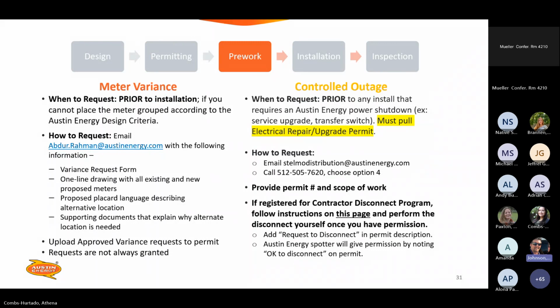A controlled outage, when to request. Prior to any installation, don't build it and try to get a controlled outage as an emergency or anything like that. You must also pull a separate electrical repair or upgrade permit, and you will request that through St. Elmo Distribution at austinenergy.com, 505-7620, choose option 4. You have to provide a permit number and scope of work, or you may not have this request granted. If registered for the CDP Contractor Disconnect Program, follow the instructions on this page and perform the disconnect yourself once you have the correct permissions.